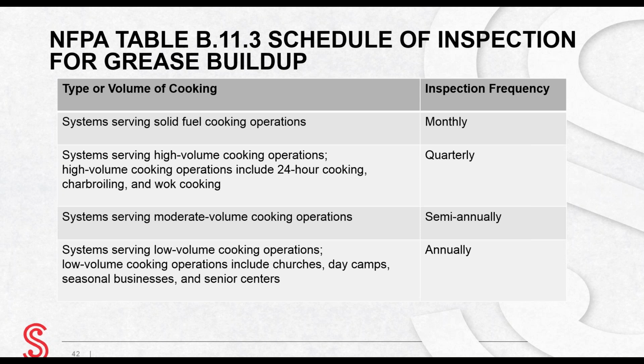If upon inspection the exhaust system is found to be contaminated with deposits from grease-laden vapors, the contaminated portions of the exhaust system shall be cleaned by a properly trained, qualified, and certified person. A properly trained, qualified, and certified person is often interpreted to be a commercial exhaust system cleaning contractor who has knowledge of and the ability to comply with NFPA 96 standard.